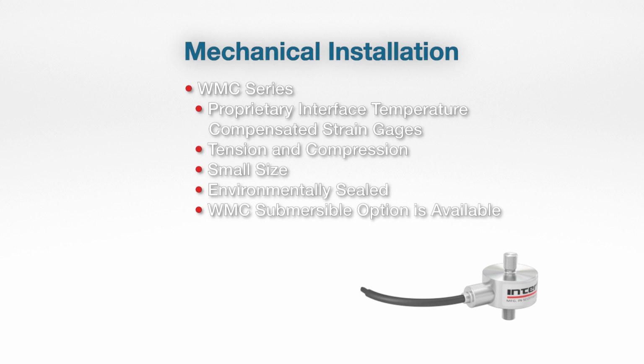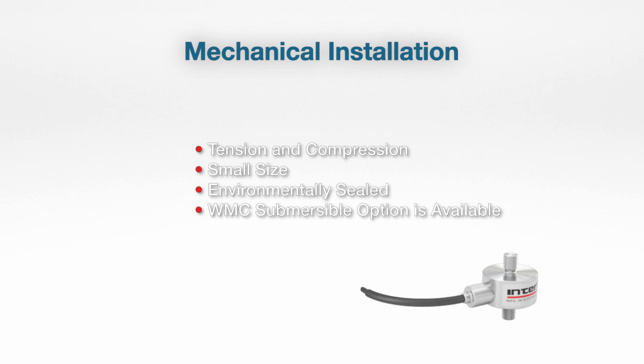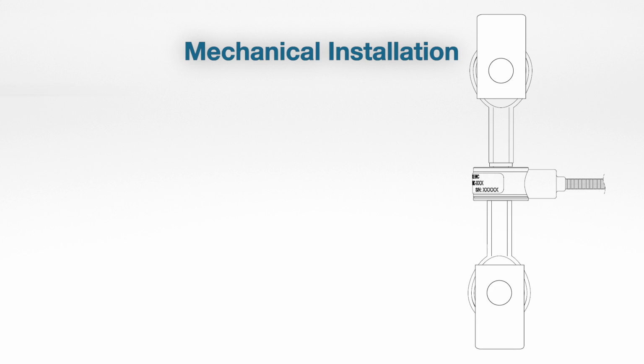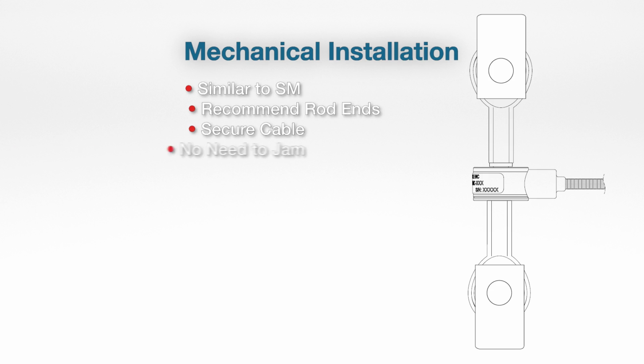All right, moving on now to our WMC series. These are very popular stainless steel load cells used for tension and compression. They're very popular due to their small size and the fact that they're stainless steel and sealed. These are often an easy go-to for doing basic testing. They have similar installation notes to the SM. Again, we'd recommend using rod ends if possible.